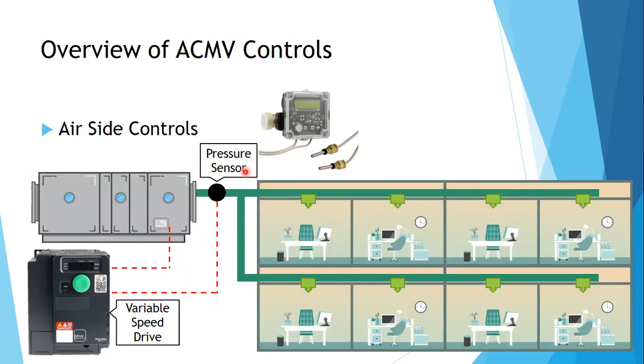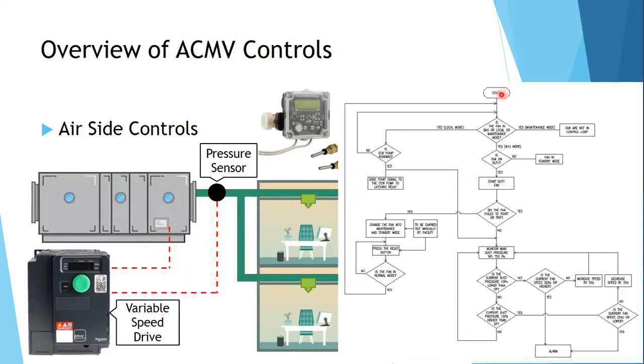This process or this flow is called control logic, the logic of how you control your equipment. So example here. This is the start. When you turn on your equipment, up to this point, assuming this pressure sensor now is maintaining at 750 Pascal. Is the current duct pressure lower or higher? If it's higher, yes. Is the current speed 50 hertz or higher? Yes or no? Then assuming that it is no, then increase the speed. So this is the control logic. This is the logic how this equipment will react, up or down, stop or slow, stop or start, whatever action you want to do, this control logic will have to determine that.